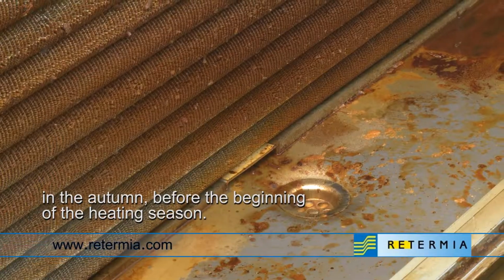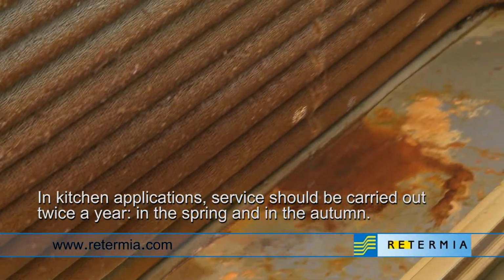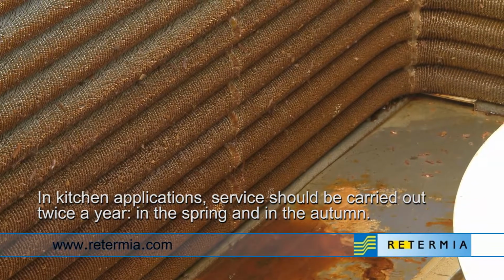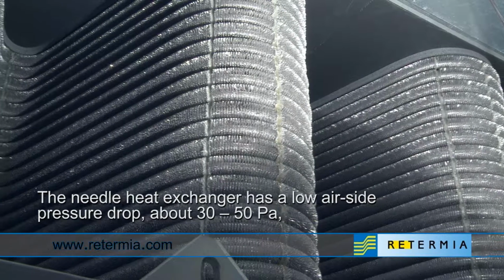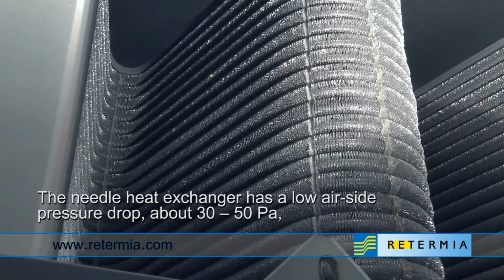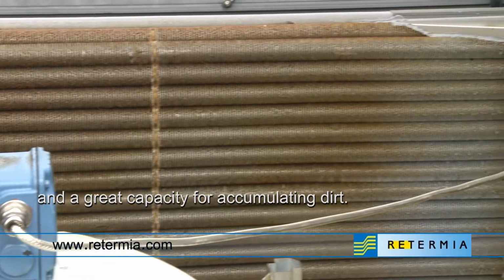Heating season. In kitchen applications, service should be carried out twice a year, in the spring and in the autumn. The needle heat exchanger has a low airside pressure drop, about 30 to 50 Pa, and a great capacity for accumulating dirt.